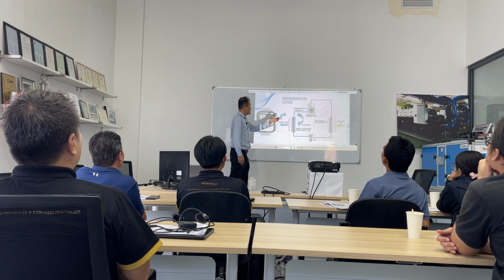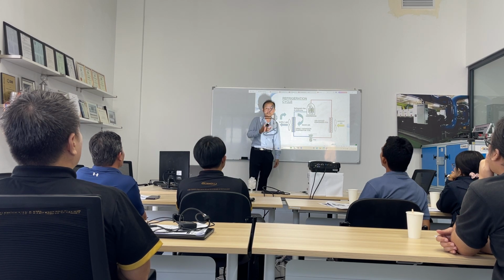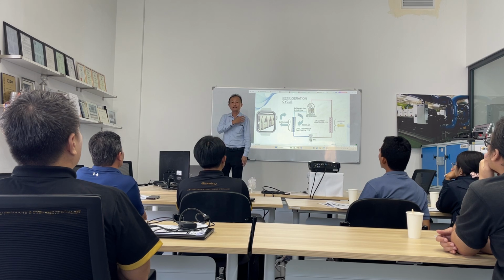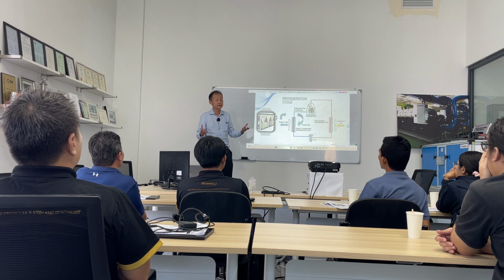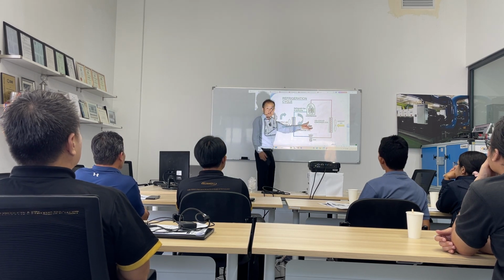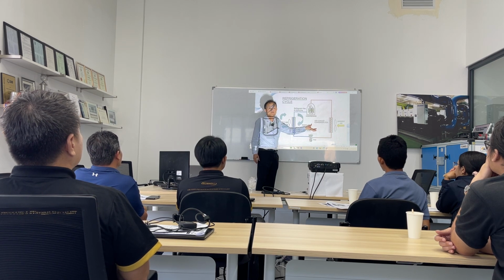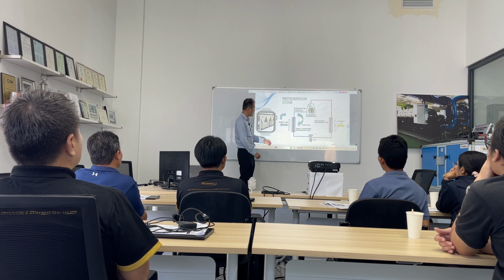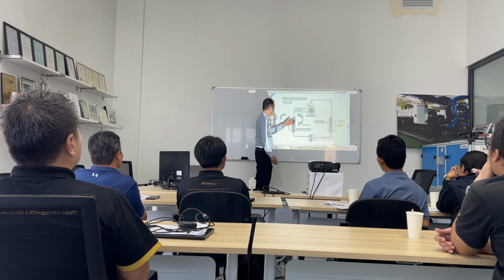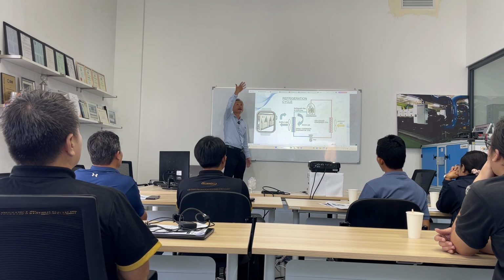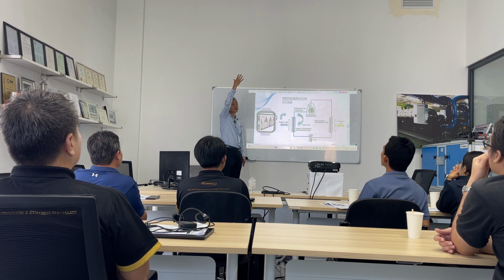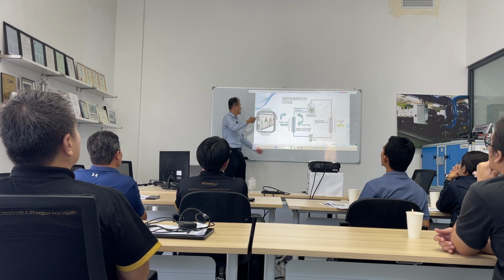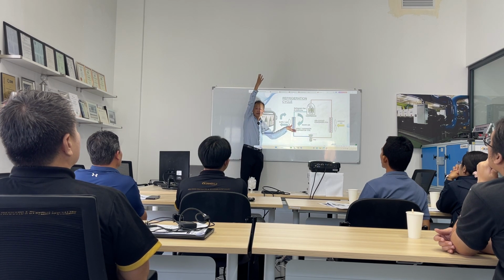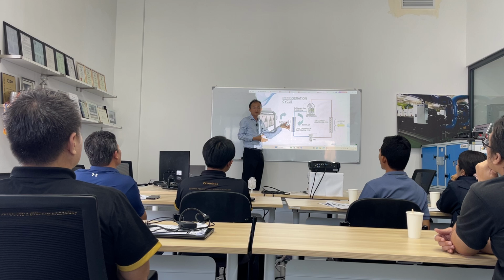Okay, so all the aircon systems, no matter how complicated they are, including chillers, are derived from this basic refrigerant cycle. Now, looking at the existing system in the aircon space here, or this room here, this is an evaporator coil inside this cassette unit. There's a cooling coil here, and a blower.